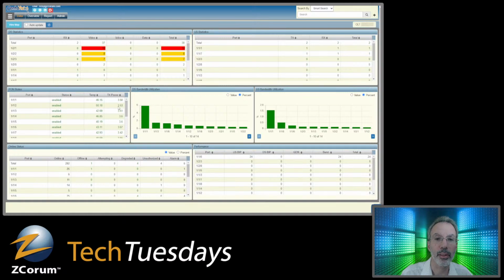Then we've got the same thing here, and I can scroll down and get more. So the way we display this on the screen is worst to best. The worst is up here on this particular port. This is the worst one. This has the most devices that are in an alert stage, and that's related to the number of devices on that port. So this is 121, and here's 121 down there, and I can't scroll because this is a screenshot. But the percentage of devices that are in an alert stage here is telling me that that is red.